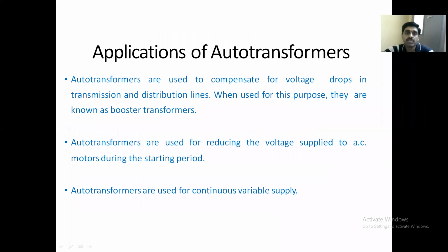Coming to applications, these are used to compensate for voltage drops in the transmission and distribution lines. When used for this purpose, they are known as booster transformers. So these auto transformers used as boosters, with a single winding on the same core, you can step up the voltage, so they are used as booster transformers. They are used for reducing the voltage supplied to AC motors during the starting period. So even for step down and step up purposes, you can see auto transformer is connected.